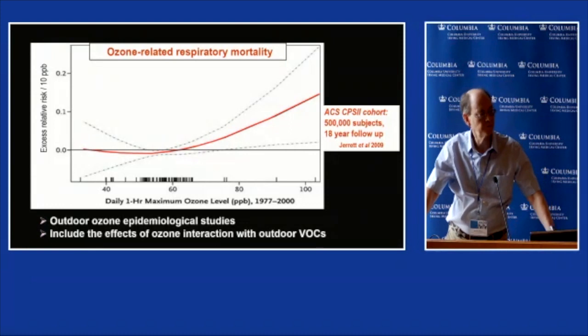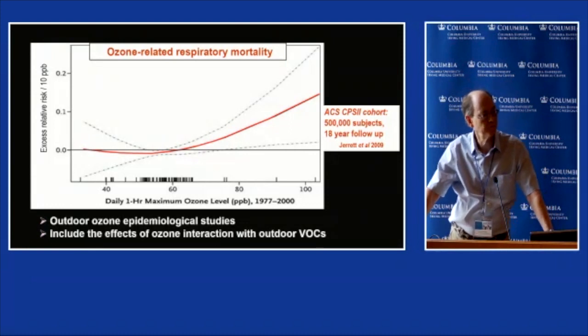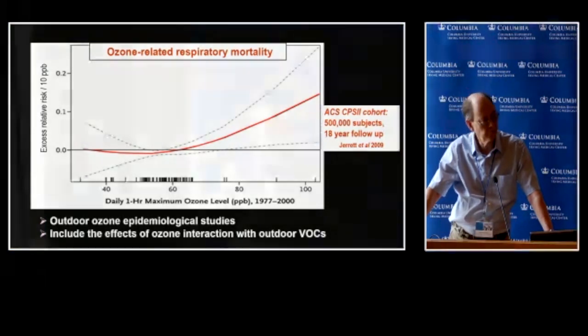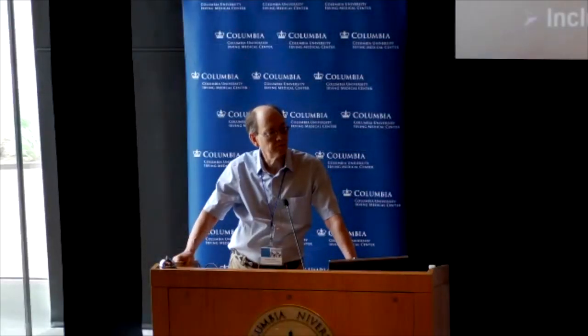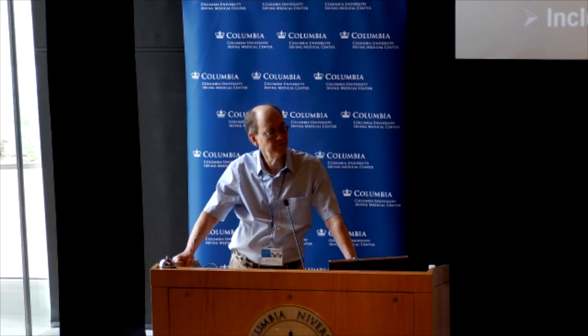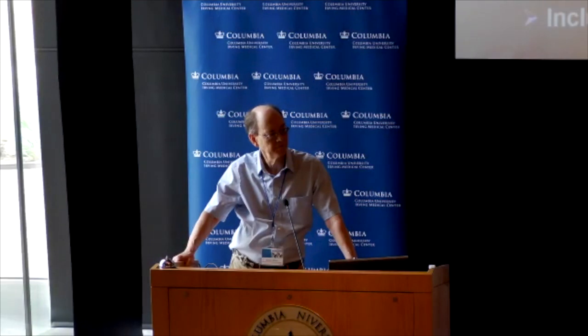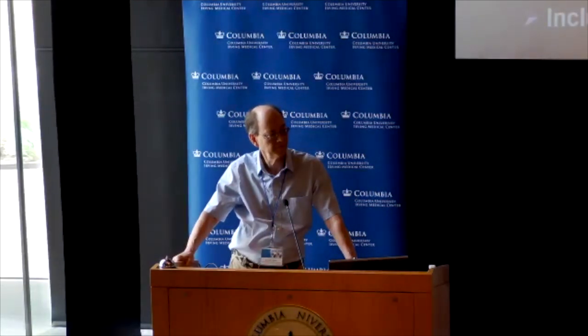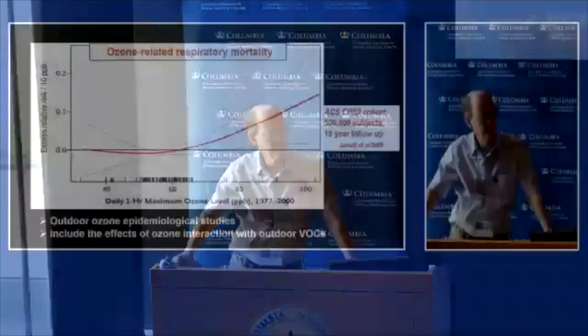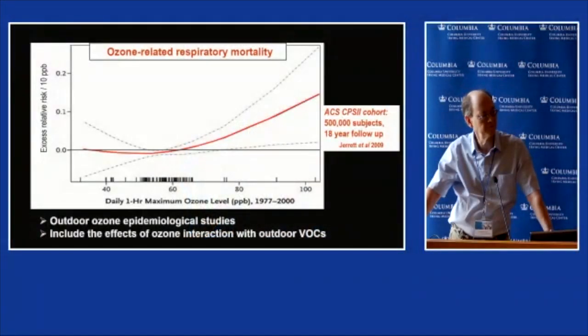Thanks for that extensive discussion of ozone. I wanted to push back. It echoes what Don said a little bit about the quick jumping to the conclusion that the answer is to cut back on the fluence rate in the room and the effectiveness of the air disinfection. We have to look for other solutions. And the reason for that is, as Don said, these infections tend to be driven by super spreader events. And if those events are under very poor ventilation, then small increments in ventilation or filtration help dramatically, as Wells Riley would suggest.